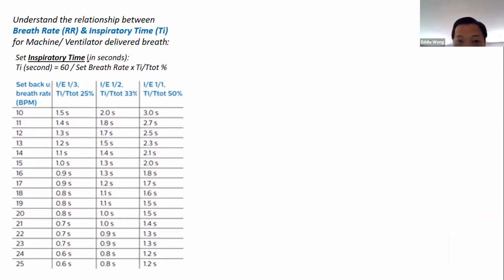Okay, maybe before I show you this, I show you the rate and I time. Upon your doctor's prescription, you see the backup rate here, 10 up to 25, right? So when you can do more breathing on your own effort, maybe you start from 10 or 12, okay? But along the time, when we need to depend more on the ventilator to deliver the mandatory breath support, then this breath per minute, this rate setting will increase, okay? And once you change the rate setting, you need to readjust your I time according to what IE ratio the doctor prescribed to you.